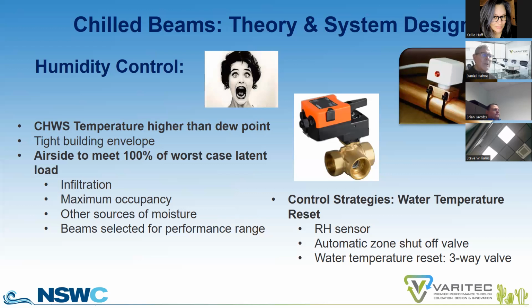If you provide your supply air with adequate dew point depression, you will control building humidity. Then I would argue is we often see when supplying 55 degree air off of a cooling coil of an air handler to serve and maintain humidity levels in the space designed at 75, 50% RH, especially in our dew point, in our monsoon season. I think we're going to always be challenged with that regard.